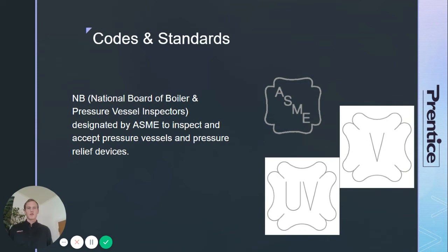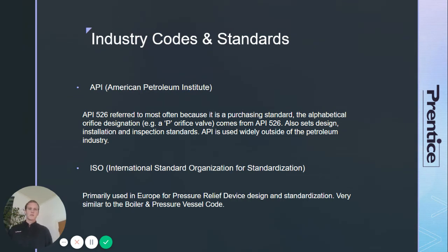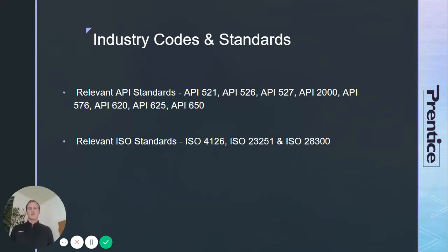If you are an operator or owner of an industrial boiler, you're probably familiar with your boiler inspector. In the US, API is the most important body outside of ASME when it comes to the design, testing, and repair of pressure relief devices. One of the most commonly referred to API codes is API 526, which standardizes not only the orifice but also the dimensions of pressure relief valves. ISO is more commonly used in Europe, but a lot of the content is the same — they give examples of how to size based on different scenarios. API is also important because they have best practices and design guidance for devices below 15 pounds gauge, so if you were designing equipment for a tank farm, API is going to be the best source of knowledge.